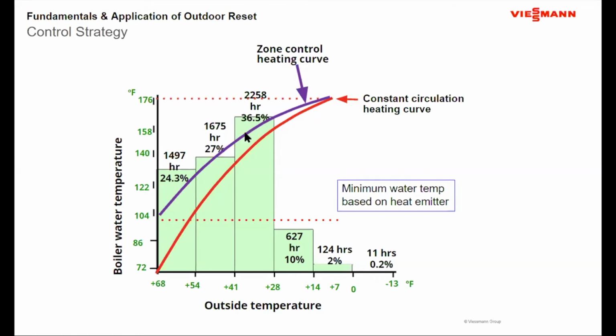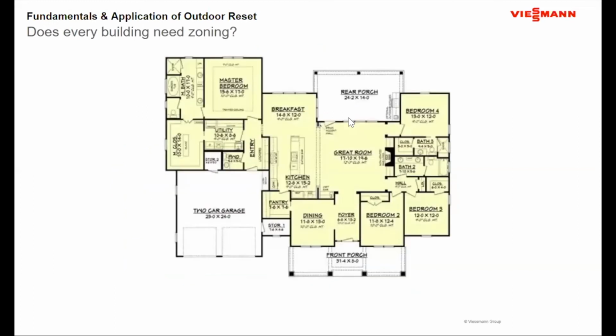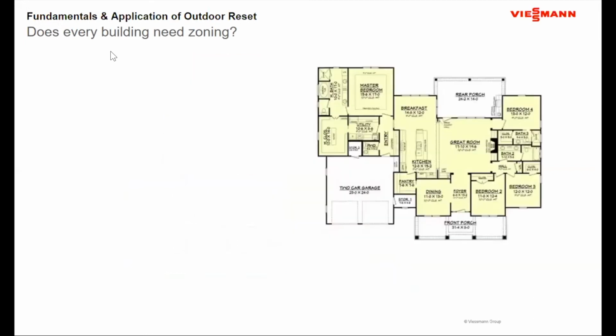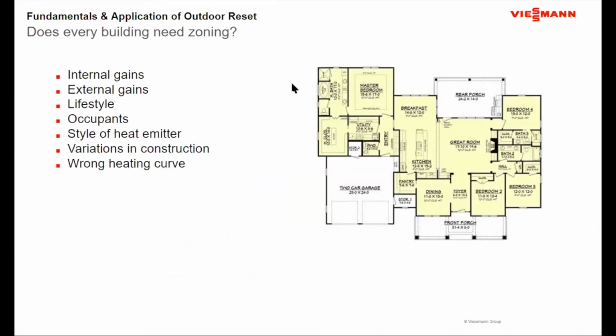The further I move out here, the more time I'm going to spend where the zone control will be off or closed. Somewhere around here, it might be a 95-5 split, 95 constant, 5% zone closed. I get out somewhere out here, that split now may be a 30-70 or maybe a 40-60 split. But from an aspect of control strategy, just because I'm doing outdoor reset, in most systems, particularly systems where there is a minimum water temperature from a heat emitter, I still want to see zoning in that building. And again, the question being asked is one that I got on a regular basis when I worked for a manufacturer's rep firm. Do I need zoning? And the reality, when you start to look at this building, is there are a lot of things that play into that zoning.